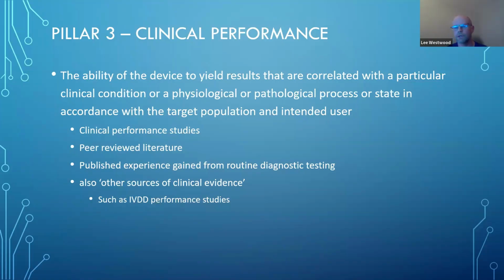But chances are your study documentation, especially if you've done it a long time ago, is not going to comply to the IVDR. But rather than rewriting it, which you don't have to do, MedTech has been quite clear on that, you can include that data as other sources of clinical evidence, and you just have to justify that. So you do a data appraisal and you justify its inclusion.